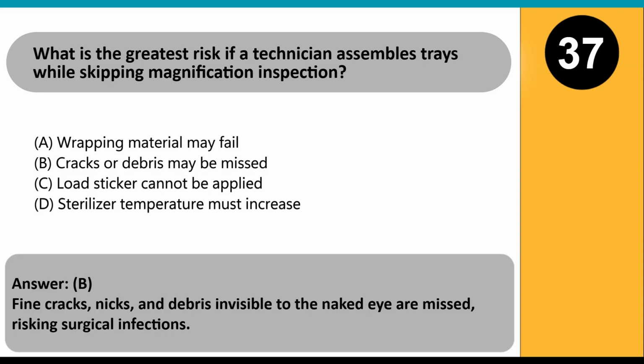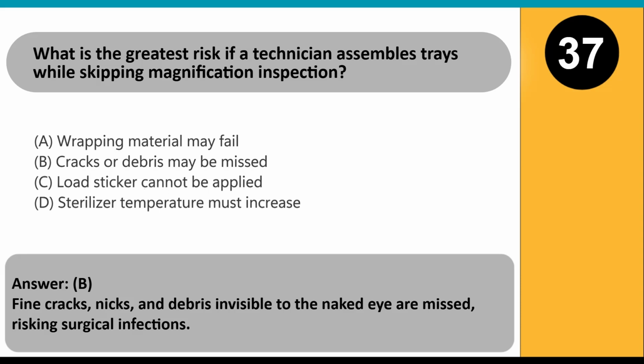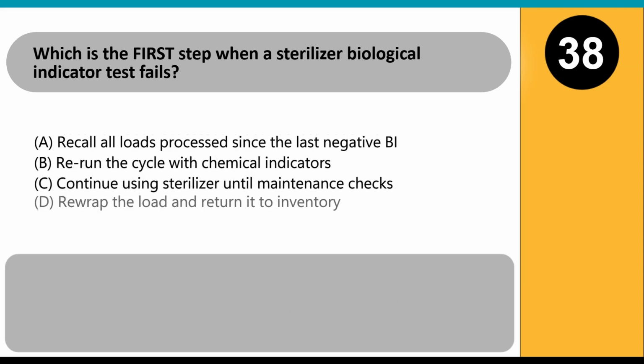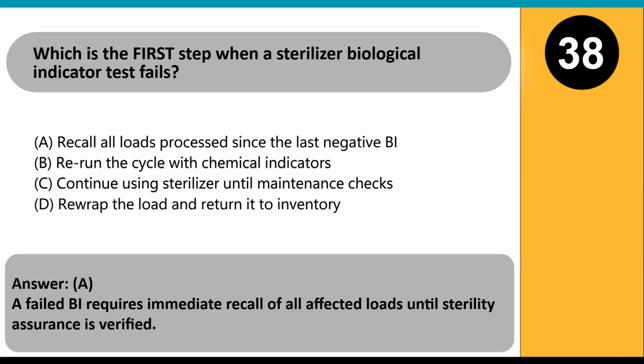Fine cracks, nicks, and debris invisible to the naked eye are missed, risking surgical infections. Which is the first step when a sterilizer biological indicator test fails? A. Recall all loads processed since the last negative BI. B. Rerun the cycle with chemical indicators. C. Continue using sterilizer until maintenance checks. D. Rewrap the load and return it to inventory. Answer: A. A failed BI requires immediate recall of all affected loads until sterility assurance is verified.